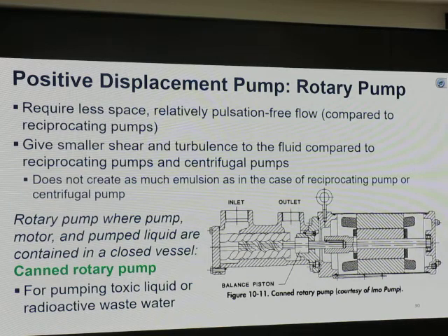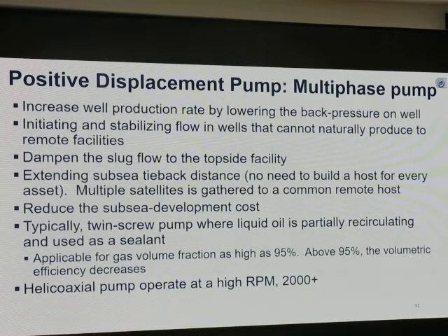Positive displacement, rotary type, can be designed to pump toxic liquid. I don't plan to test you on which pump can handle toxic liquid because we normally don't have that. But just so you know, for toxic liquid there are certain pumps, called canned rotary pumps, that can handle that. Multiphase pump can be used for subsea facility, extending subsea tieback distance to multiple satellites, and reducing the subsea development cost. So installing this multiphase pump in the subsea will reduce the development cost.